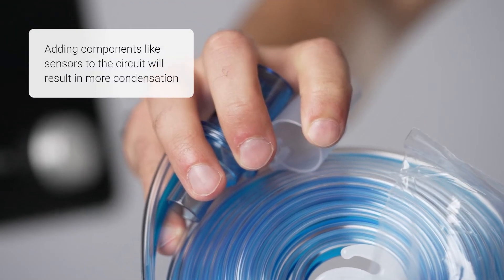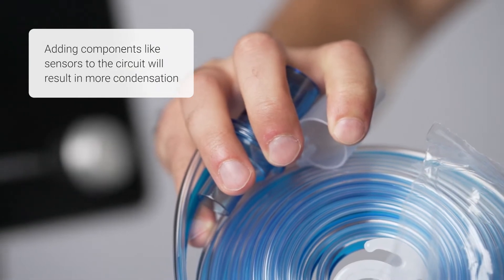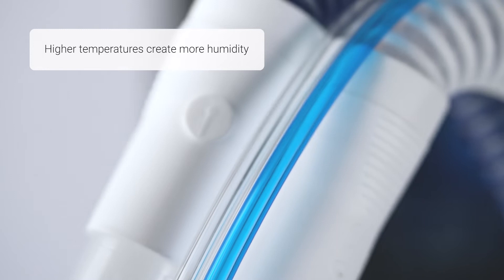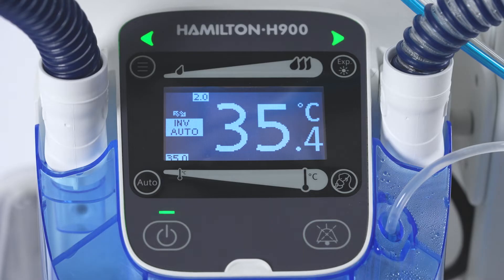For example, adding components like sensors to the circuit will result in more condensation. It is important to be aware that higher temperature settings on the humidifier chamber create more humidity.